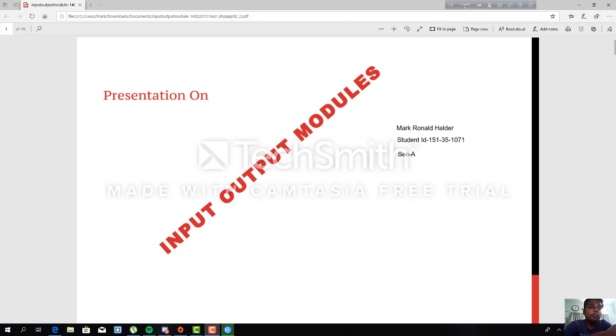And the last one is output word assignment. The 1746-NO4V is a 4-channel analog voltage output module. 4 words will be assigned to the output status table as part of the I/O configuration. A module in slot 4 will have words O:4.0 through O:4.3, one for each channel. This is the end of my presentation, and thank you.